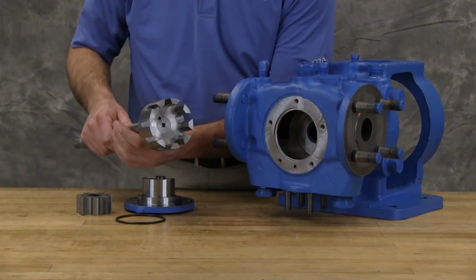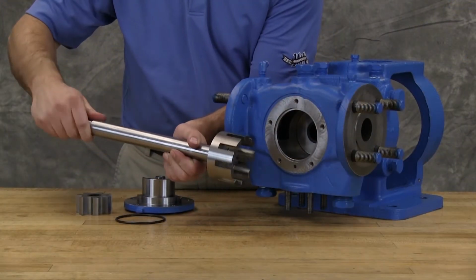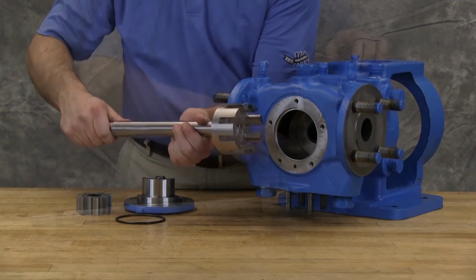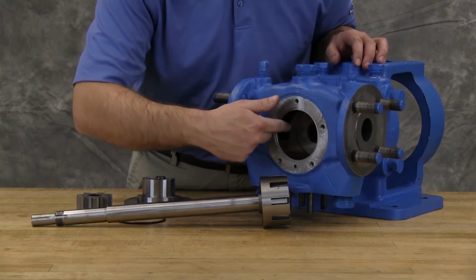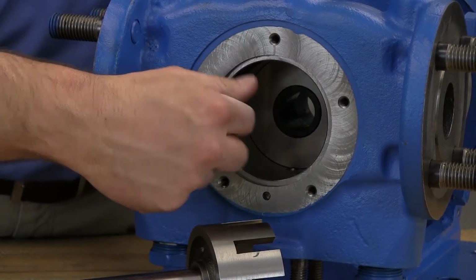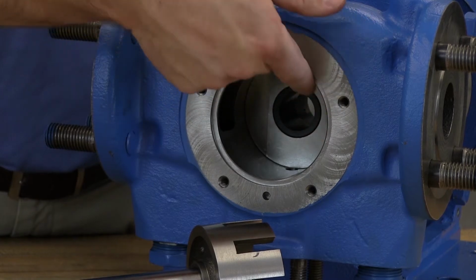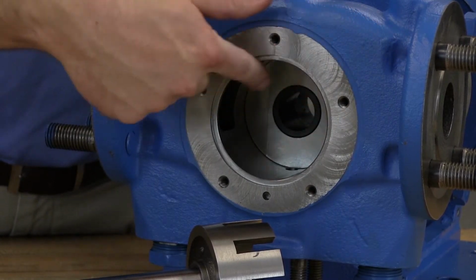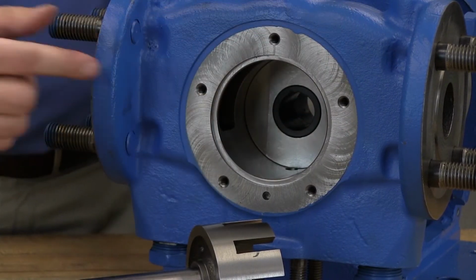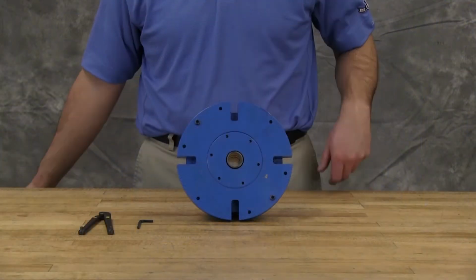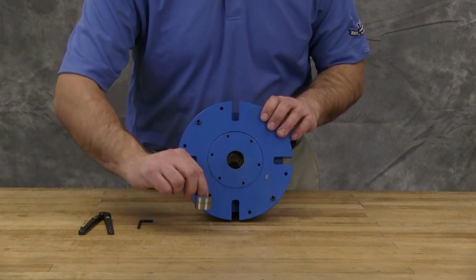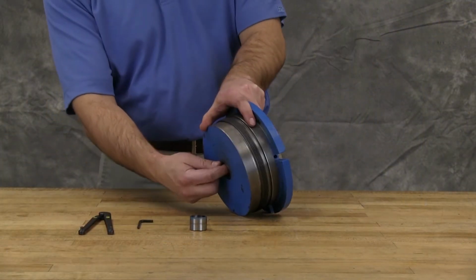Burrs left on the shaft can damage O-rings on the seal sleeve during installation, so they should be removed with a fine grade of emery cloth. Replace any worn components. Clean the rotor hub and casing bore. Make sure both are free of dirt or grit. Now the bearing housing can be disassembled. Begin by removing the spacer collars.